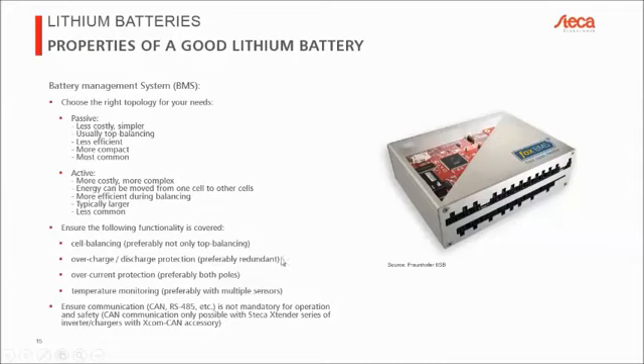Then you need preferably redundant overcharge or under-discharge protection to disconnect the battery whenever you're in a dangerous state. We need some form of overcurrent protection and some temperature monitoring. You don't necessarily need to monitor every cell, but some cells should be monitored to make sure the pack isn't running too hot.